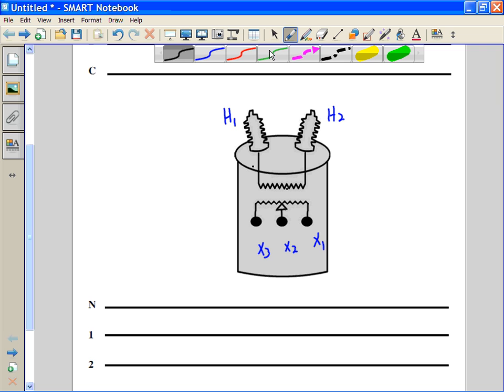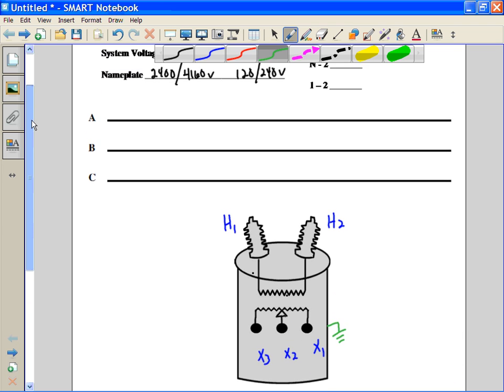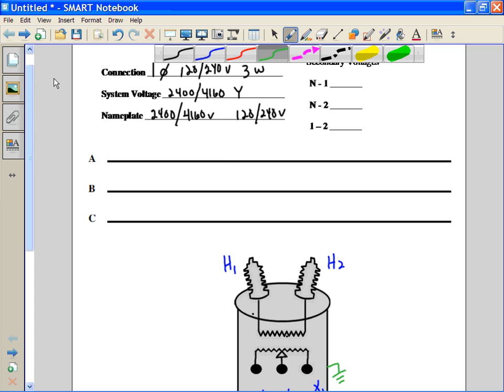It's a good idea when you're making these drawings to take care of the important things such as grounding, showing our grounds. The same is true in the field when you're making the connections. Probably the most important connection you can make is the tank ground, and also to assure that the neutral is tied in with the grounding system as well. So let's go up and make our primary connection.